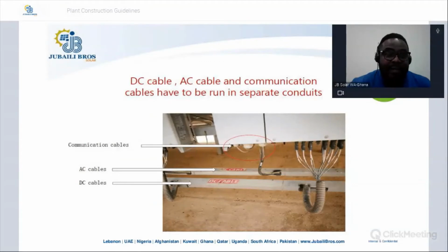Okay, it's always crucial that you conduit them in separate conduits. AC cables separately, DC cables separately, communication cables especially. We don't advise that you conduit them with the power cables, at least. Absolutely not. Okay, this is even for general inverter systems, not only for Huawei. So let us make sure that the conduit is done properly. We will discuss this even more when we come to MBUS or PLC. Okay, PLC communication.